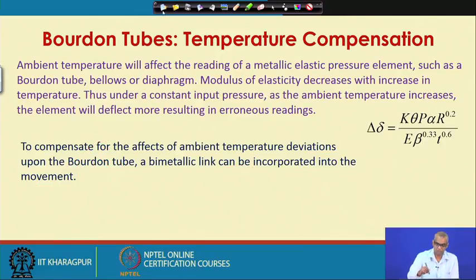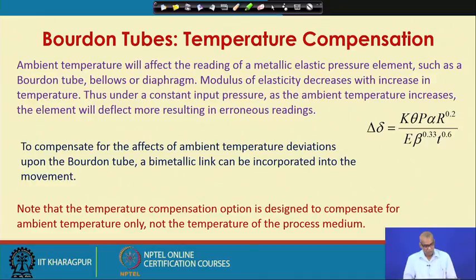So, if you attach this bimetallic strip to the link of the Bourdon tube, these two will cancel each other out, and the net deflection of the tip of the Bourdon tube will now be free from the effect of ambient temperature. Note that the temperature compensation option is designed to compensate for ambient temperature only, not the temperature of the process medium.